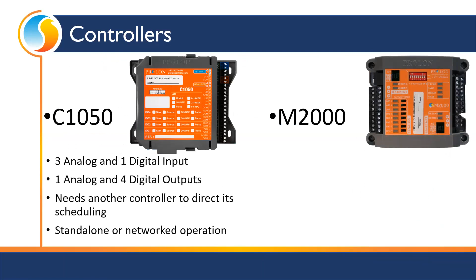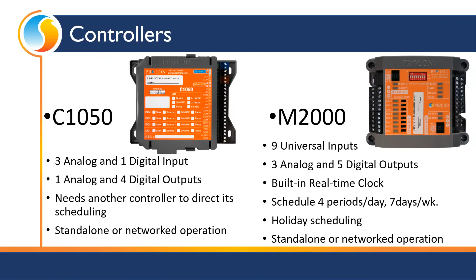And because we reuse the same hardware over and over, and all that changes is the software, say if you remodel the building and you had an M2000 rooftop unit for a zone system, and it's like, well, we're taking that out and we don't need that anymore, but I really need a single zone system in here. We can reprogram that controller. Your contractor can do that in the field with the software that they already have available to them. So it's not like, well, this controller is junk, we've got to throw it out and go buy something new. No, we'll just repurpose it and continue on down the road.